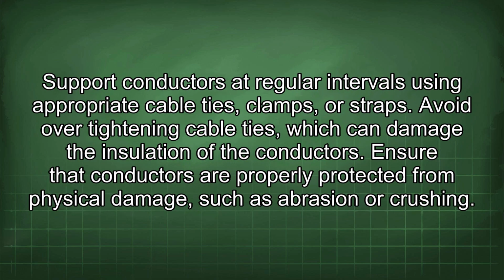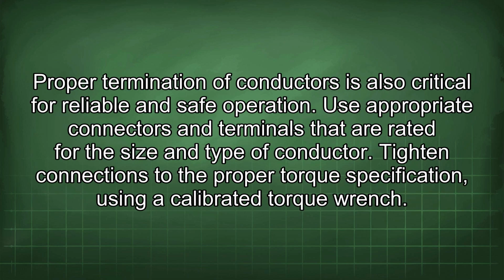Support conductors at regular intervals using appropriate cable ties, clamps, or straps. Avoid over-tightening cable ties, which can damage the insulation of the conductors. Ensure that conductors are properly protected from physical damage, such as abrasion or crushing. Proper termination of conductors is also critical for reliable and safe operation.